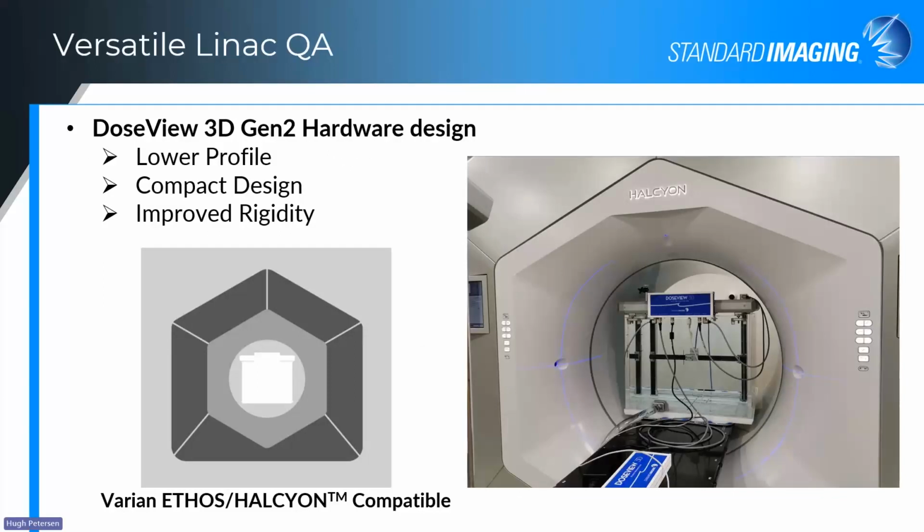Another point, it's a very versatile system. About 4 years ago, I guess, we redesigned the tank itself with a little bit lower profile, a little more compact design. With the advent of the Halcyon and Ethos systems coming out from Varian, we needed to make a system that was compatible with those, and we've done that with the new system. And bringing it down a little bit also improved the rigidity and the accuracy of the water phantom as well.